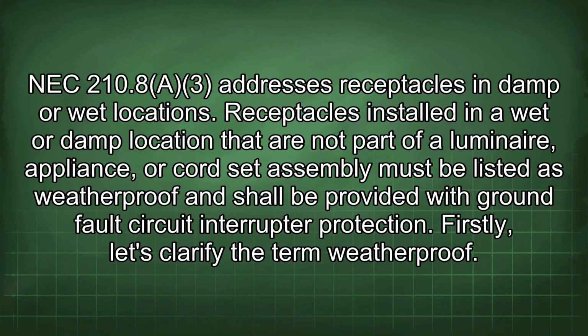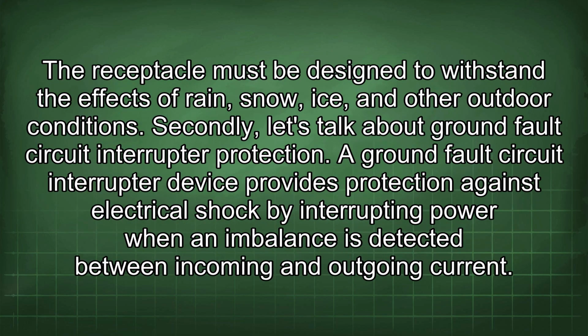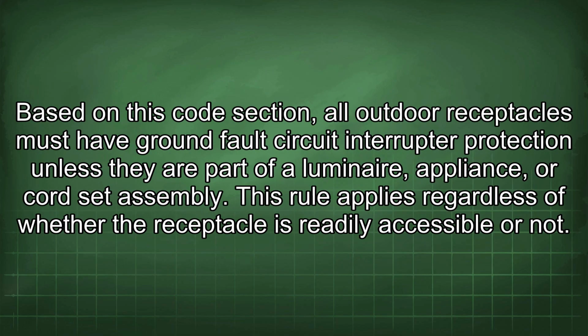Firstly, let's clarify the term weatherproof. The receptacle must be designed to withstand the effects of rain, snow, ice, and other outdoor conditions. Secondly, let's talk about ground fault circuit interrupter protection. A ground fault circuit interrupter device provides protection against electrical shock by interrupting power when an imbalance is detected between incoming and outgoing current. Based on this code section, all outdoor receptacles must have ground fault circuit interrupter protection unless they are part of a luminaire, appliance, or cord set assembly.